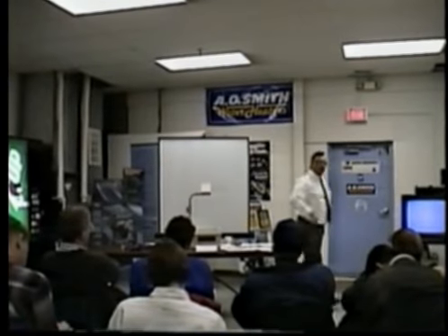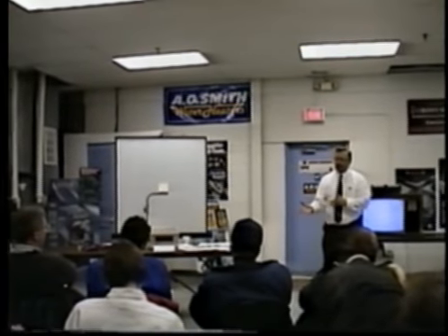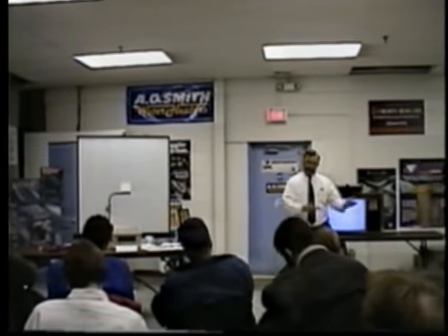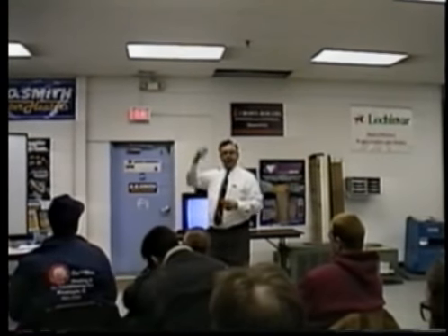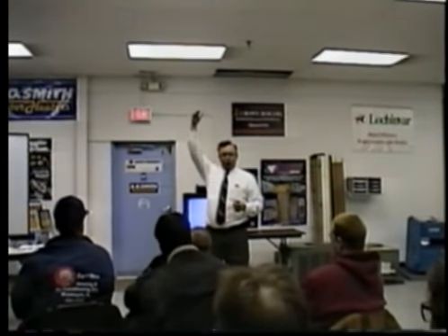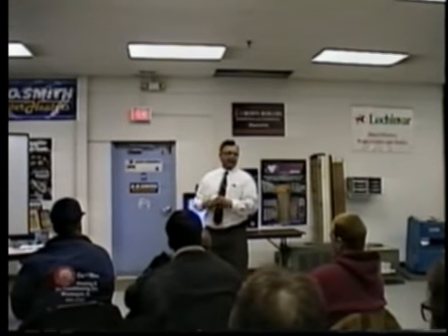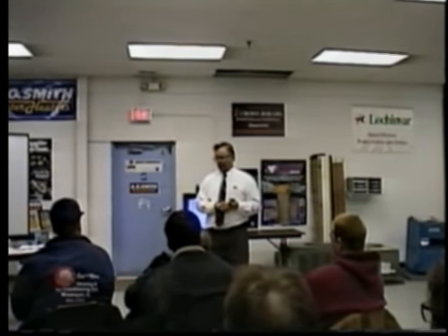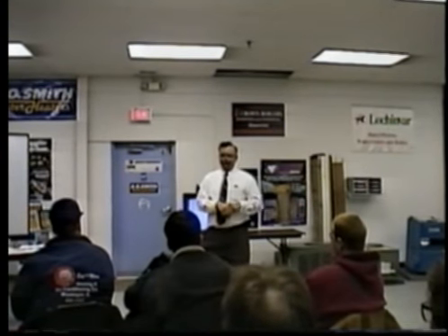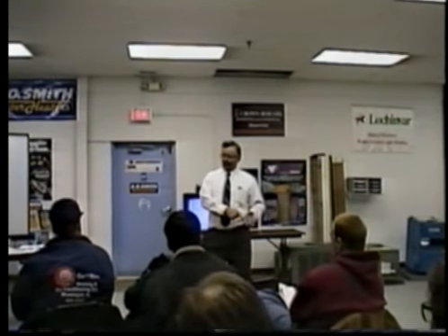And the point is, if Scott's air conditioner was not big enough to handle the humidity and the sensible heat, he would have an excellent dehumidifier for his house. So if it's 100 degrees outside, his house might get down to 92, and he'd be nice and dry, like Arizona, inside of his house. But he doesn't want 92, he wants cooler than that.